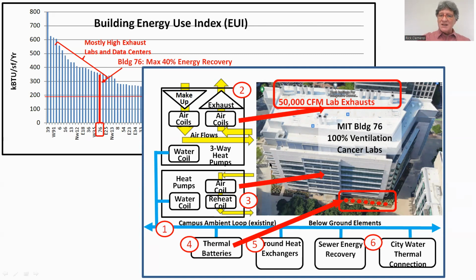So this is a heat pump solution in the exhaust recovery, and a heat pump solution for the buildings, all connected to this ambient loop. That way you get this maximal diversity going on campus—diversity across a building, the side the sun's shining on versus the side that's not, different rooms, different temperatures, and around the campus all the different kinds of loads, like dining facilities versus labs versus offices versus residential. And we know the residential is not on this chiller loop yet, but it will be eventually.